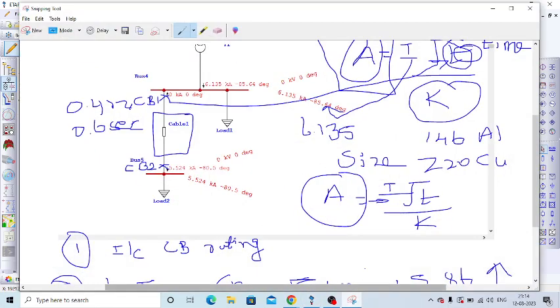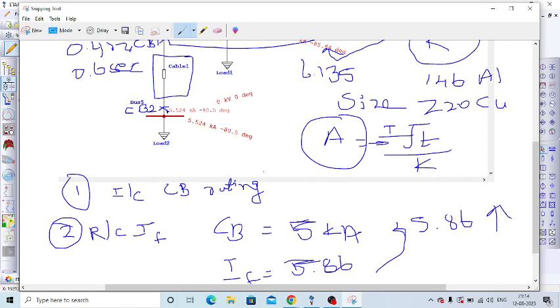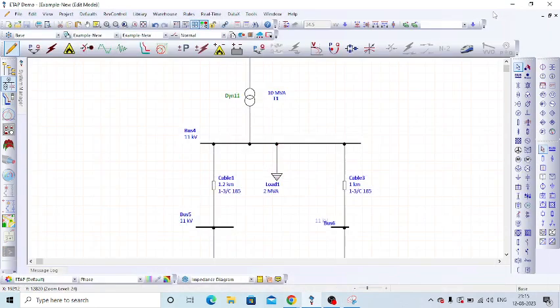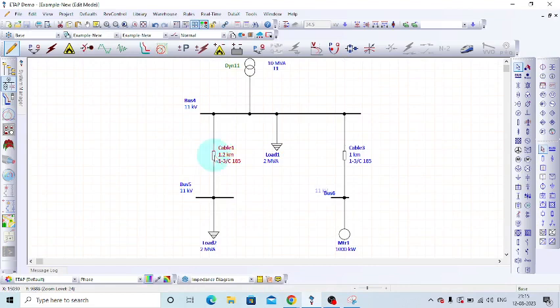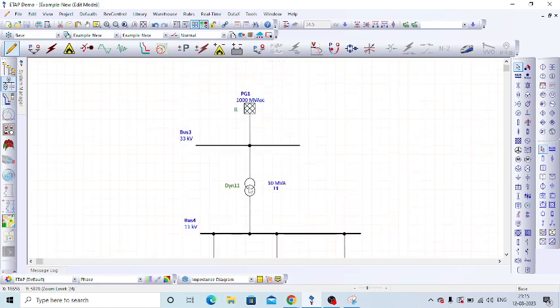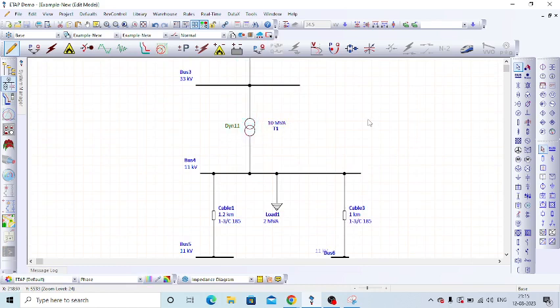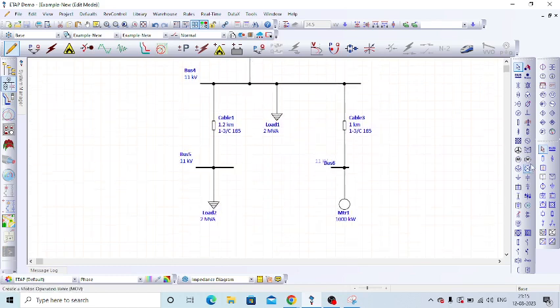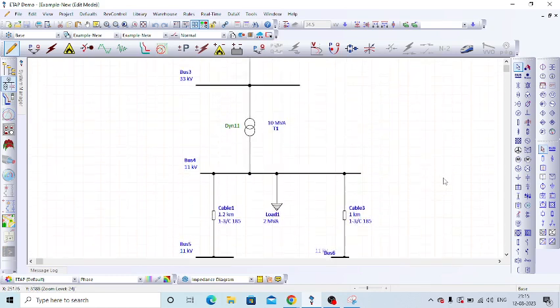So totally, how to manage the situation: the first option is to increase the circuit breaker rating. In the second option, we have to reduce the fault current, and we can reduce it in multiple ways. One option is to increase the cable impedance by increasing the cable length. The second option is to increase the transformer impedance. The other option is introducing the fault current limiting reactor. This also we can do to reduce the fault current.